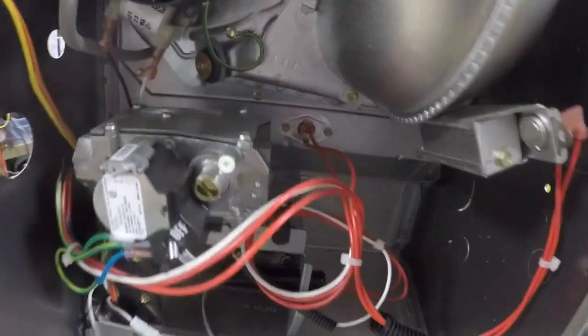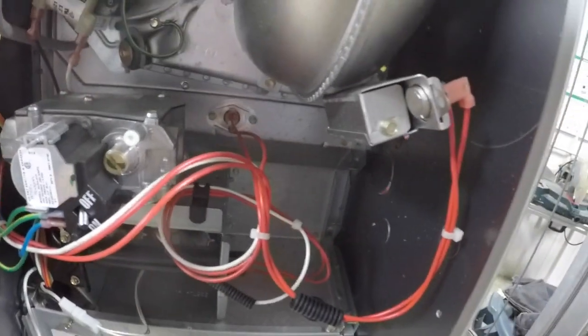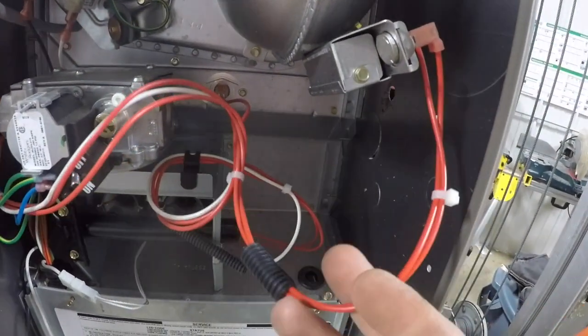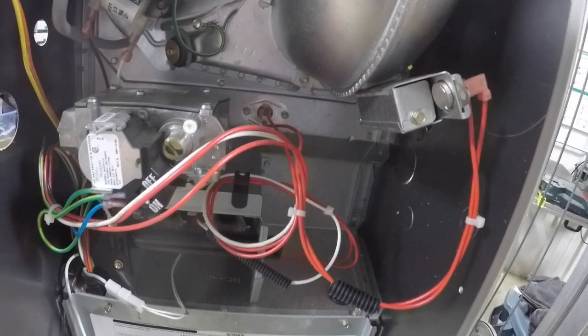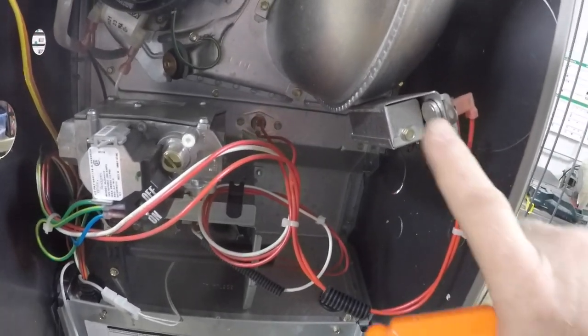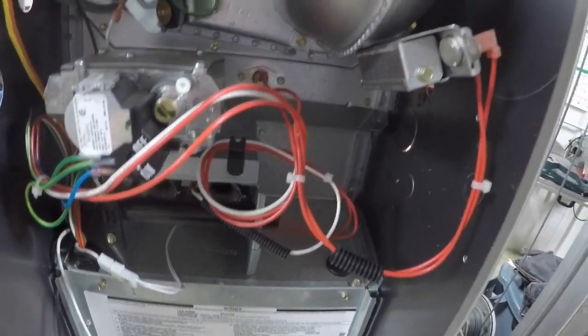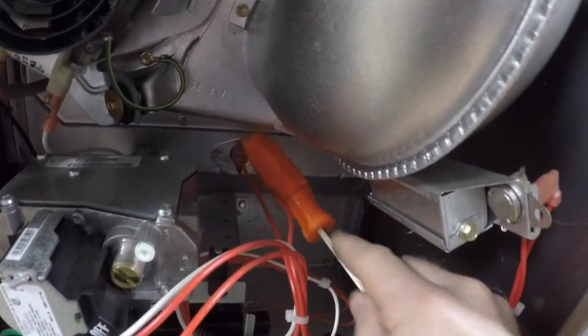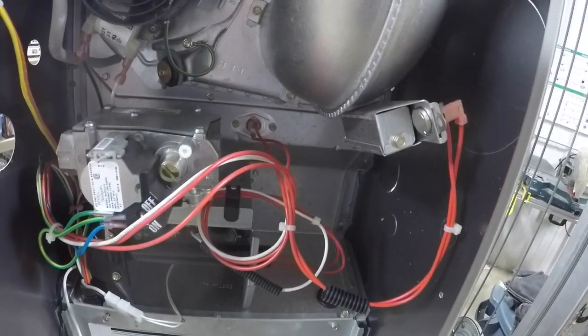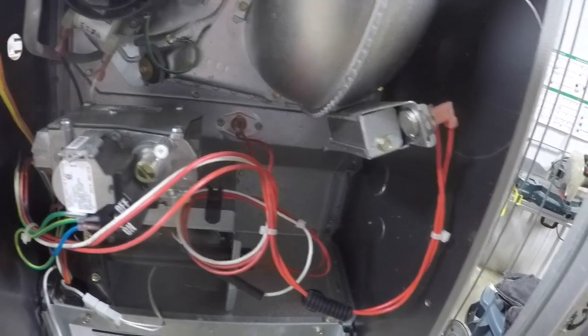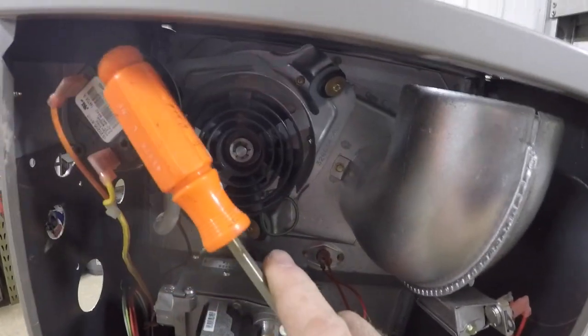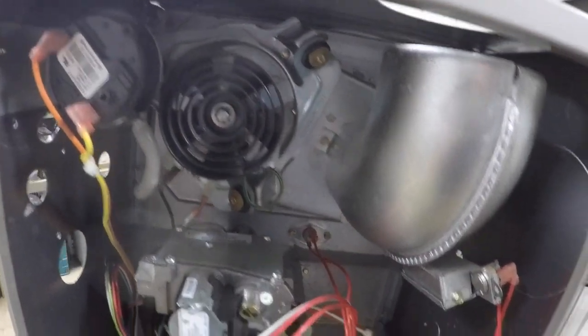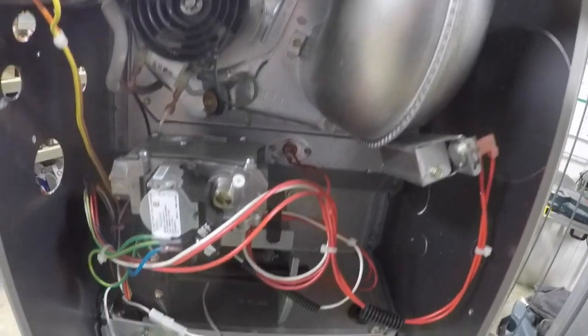This is the inside of an 80% efficient furnace. And it's got a low voltage, that's these wires right here, a low voltage series safety circuit, which has a whole bunch of special switches and sensors that are there to make sure that your furnace is operating properly. For instance, there's a switch way in the back here called a high limit. If your furnace were to overheat, that would make your furnace not work. Here's another temperature sensor. The video I'm posting today talks about this piece right here, which is a pressure switch. That's designed to make sure that your furnace is venting properly.